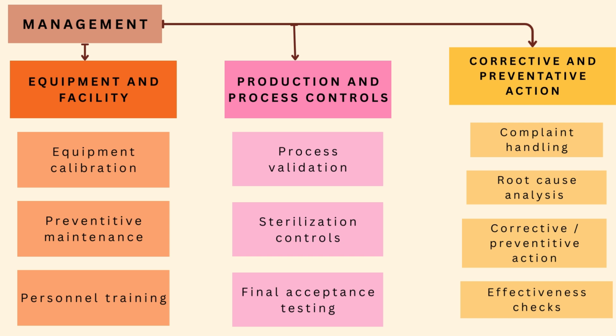As for production and process controls, this governs how the stent is actually manufactured. This includes validated manufacturing processes, sterilization controls, and final acceptance testing. For an implantable coronary stent, these controls ensure that each device released meets predefined specifications for safety and performance and can be repeatable in manufacturing. As for the CAPA, or corrective and preventative action, it serves as the feedback mechanism of the QMS. Complaints, deviations, and non-conformances trigger investigations through root cause analysis. Corrective actions address existing issues, while preventative actions reduce the likelihood of recurrence. Together, all of this ensures manufacturing issues are detected early and corrected before they impact patient safety.